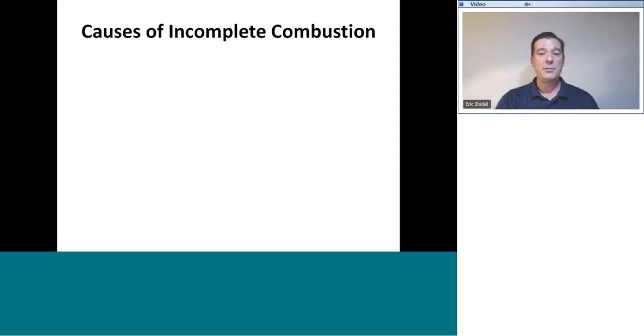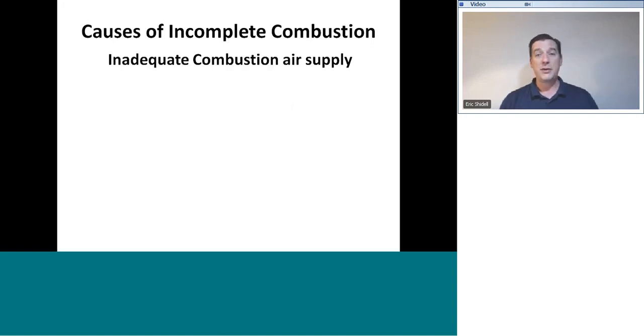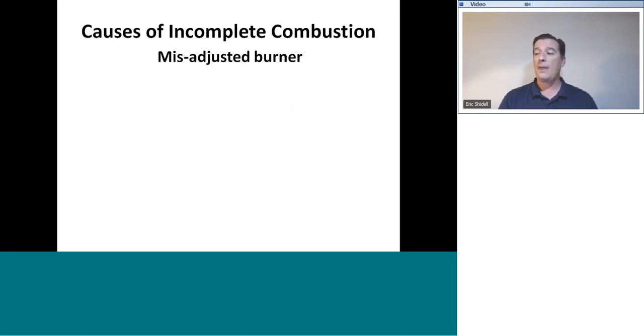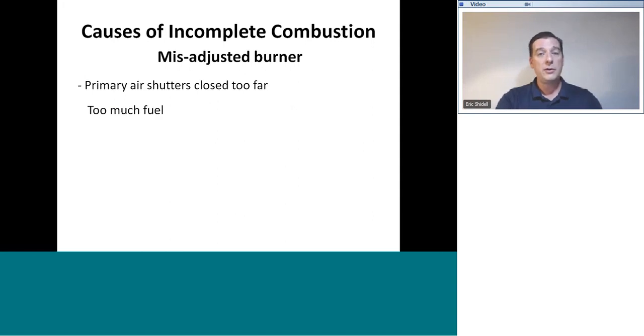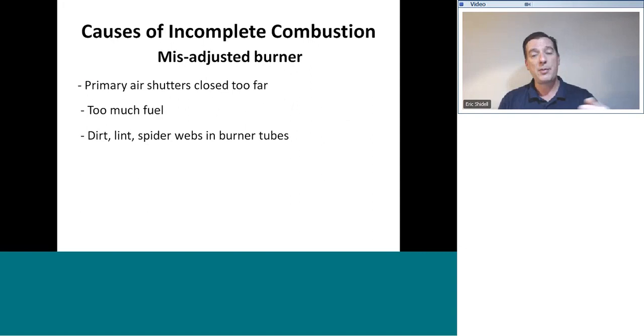So where does incomplete combustion come from? Well, not enough combustion air supply is one good source. Not built to code. Too tight a construction. Somebody boxed in the boiler or the furnace and put a door on it, and it doesn't allow enough air to come in. Misadjusted burner. The air shutters closed too far. Too much fuel delivery. That's an adjustment that we are in charge of. Dirt, lint, or spider webs in the burner tubes. That's something that's cleanliness. We need to keep these burners clean.